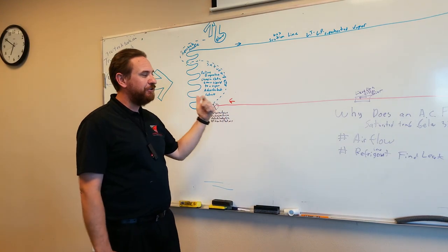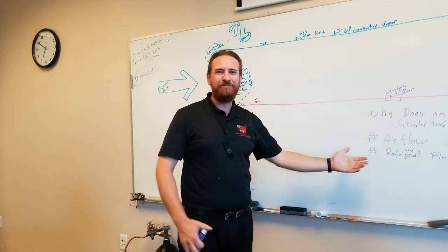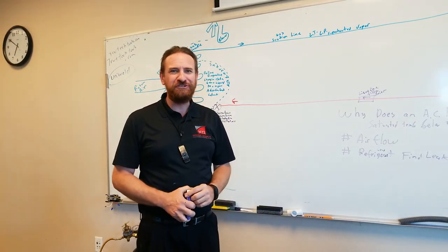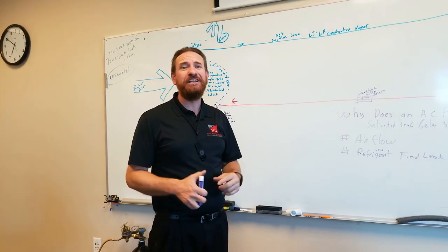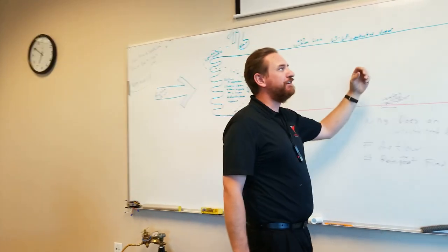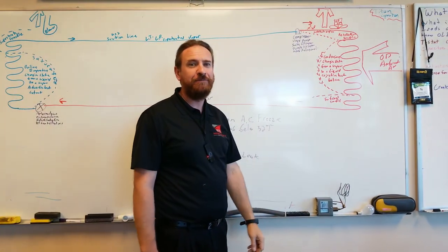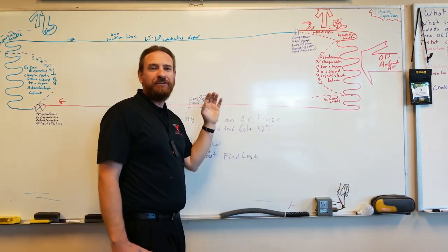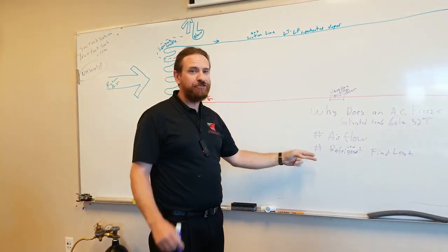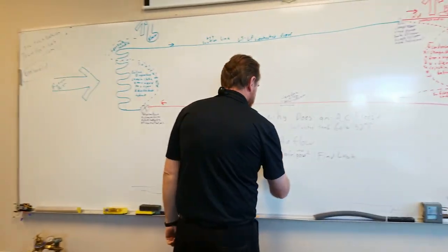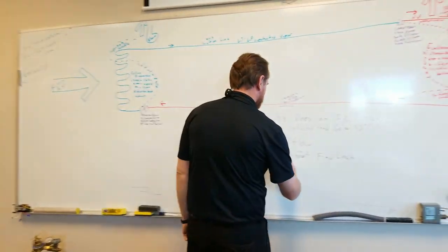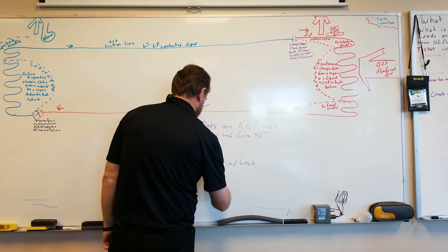So number one cause is airflow. Number two cause is low refrigerant — and if it's low, there's a leak. Most systems across America are overcharged. Refrigerant is not magical cooling juice or antifreeze — it absorbs massive amounts of BTU by changing state from liquid to vapor, and rejects massive amounts of BTU condensing back to liquid. Number three, and easy to identify quickly, is temperature — specifically, low temperature.